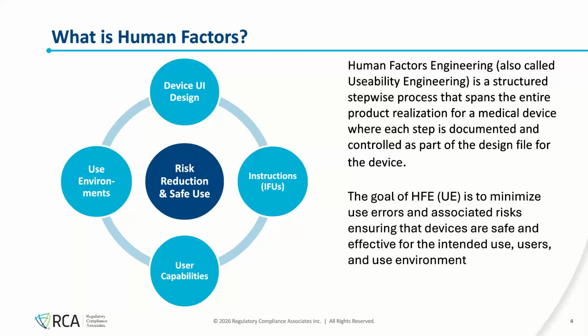What is human factors? The reason we gather here. It is commonly referred to as human factors engineering, also called usability engineering. It is a stepwise process. It spans the entire product realization process for medical devices, where each step is documented and controlled as part of the design file. The goal of human factors engineering or usability engineering is to minimize use errors and the associated risks that are associated with use of medical devices. It helps ensure safe and effective use for the intended users in the intended use environment based on the intended use of the device itself.